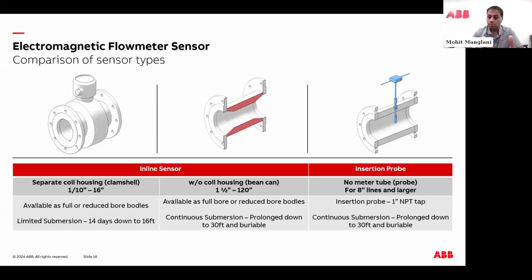These are typically used to save money on larger lines. Obviously, a 60-inch mag meter will cost a lot more than a mag on a stick, and you can still get a flow indication. Mag meter accuracies on the inline sensors can go all the way down to 0.2% of actual flow rate, depending on the velocity. Insertion probes are typically 2% accuracy, assuming they're installed the correct way. The nice thing about the insertion probe and the one without the coil housing is that they're both rated for continuous submersion, down to 30 feet. But depending on your application, a clamshell is lower cost, and most applications don't require the heftiness that these have, whereas this one meets most applications.